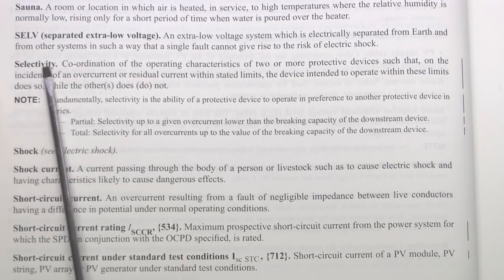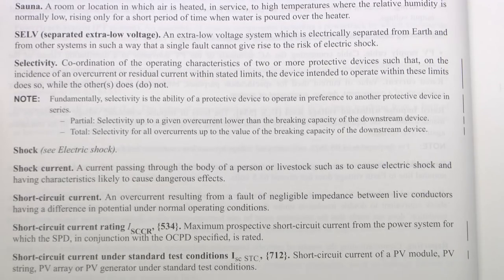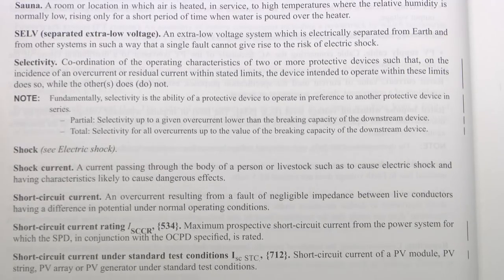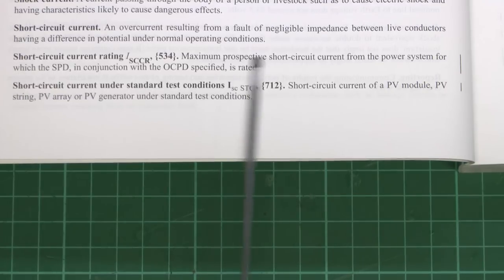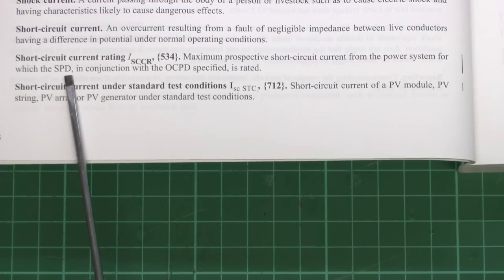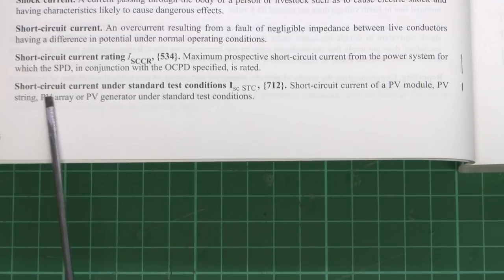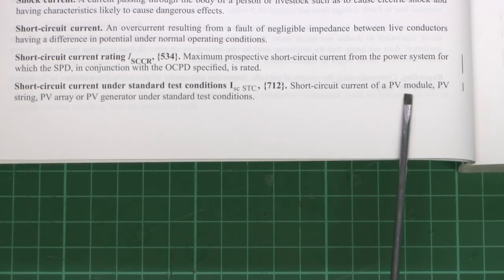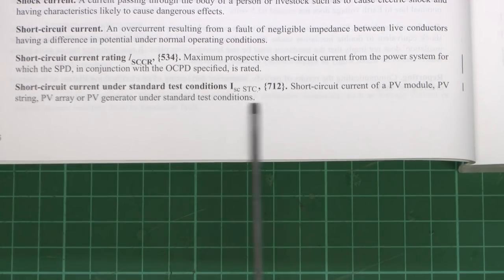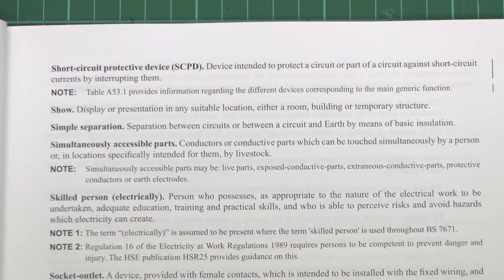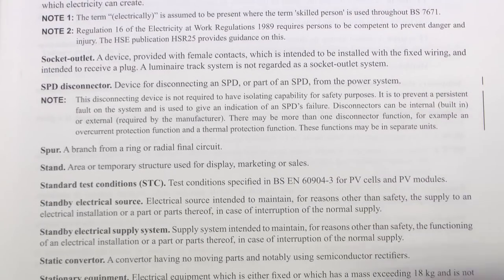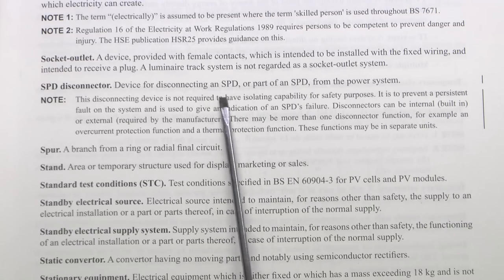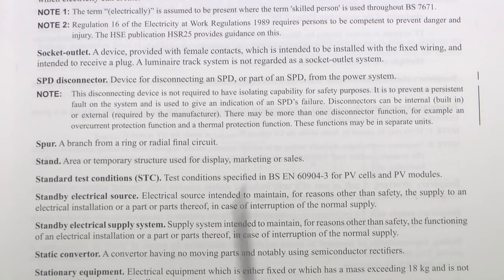Selectivity is another new one, which as we've already seen was what used to be called Discrimination. And at the bottom of the page we've got the Short Circuit Current Rating, or ISCCR, which is the maximum prospective short circuit current from the power system for which the surge protective device in conjunction with the overcurrent protective device specified is rated — explained in section 534. We also have Short Circuit Current Under Standard Test Conditions, which is relevant to PV modules, or photovoltaic solar panels. And on the line of surge protective devices, we've got the SPD Disconnector, which is a device for disconnecting a surge protective device from the power system.